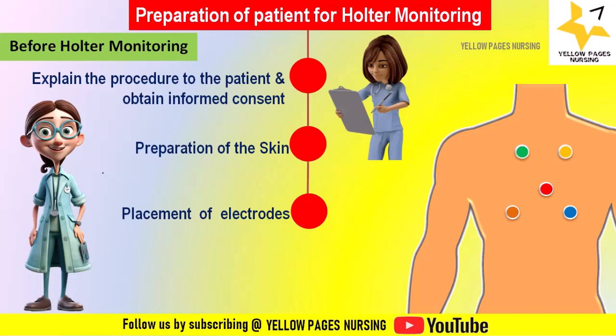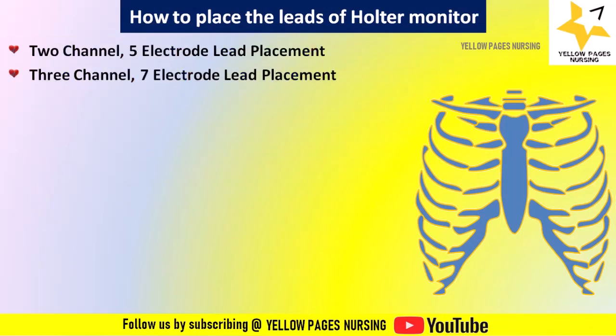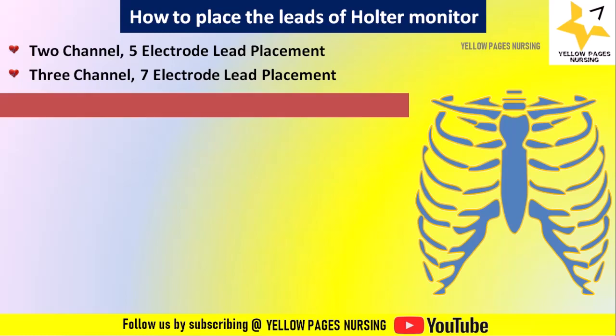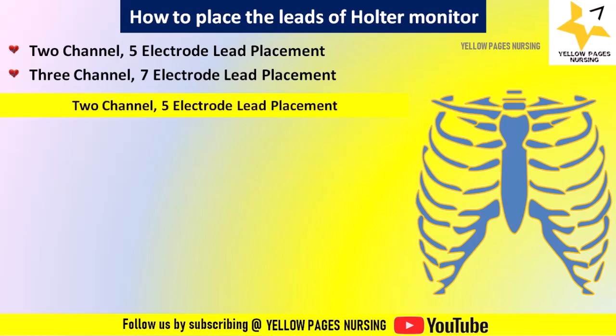The most common lead configurations are 2-channel 5-electrode and 3-channel 7-electrode lead placement. These channels constantly monitor and record ECG data for 24 to 48 hours. For placement, follow the manufacturer's guide or reference to place the leads.